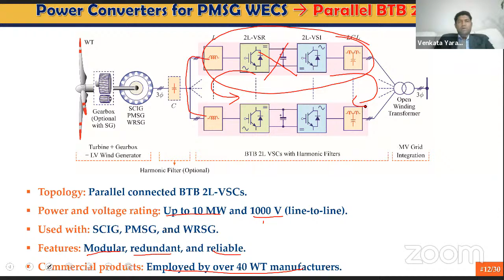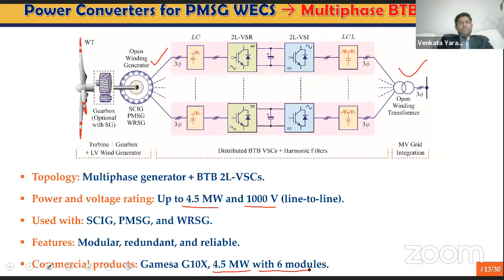The next configuration is multi-phase. If I go back to the previous slide, we see that these converters are connected in parallel. When converters are connected in parallel, we have a problem of circulating currents on both the generator side as well as the grid side. We can avoid the problem of circulating currents by using a multi-phase generator and a multi-phase transformer. Here, because the windings are electrically insulated, we don't have the problem of circulating currents, and we still have all the benefits that we discussed earlier. This topology is available up to 4.5 megawatts and 1000 volts. It is commercialized by Gamesa with up to 4.5 megawatts with 6 modules in parallel.